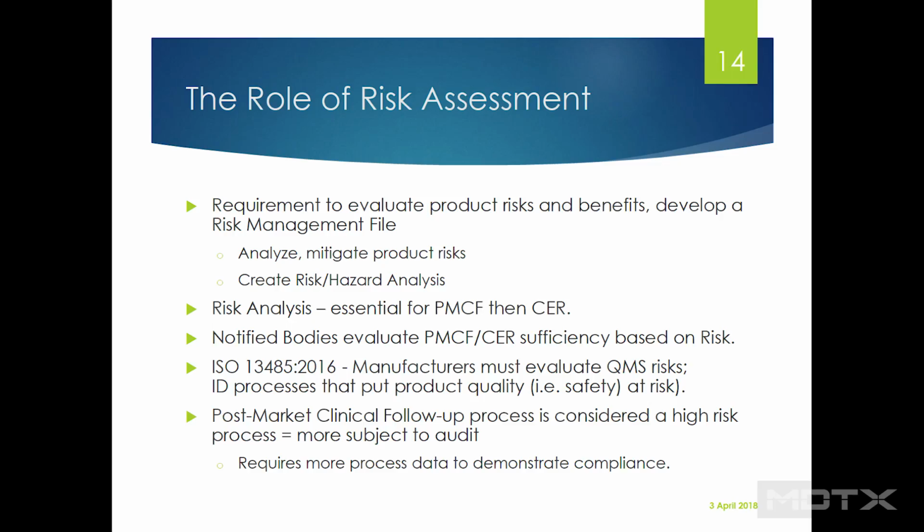Okay, role of risk assessment. Can't really overemphasize the role of risk assessment. It's affecting everything these days. It's just constantly increasing. Every medical device manufacturer, regardless of market, is required to evaluate the risks and benefits of the product and have a risk management file to analyze and mitigate, as far as possible, that's a change in the language, the risks for that product. The risk analysis is a crucial element for the PMCF. It's also affecting, obviously, the resulting CER. So a deeper emphasis on risk management and risk analysis in the changes to the CER requirements.